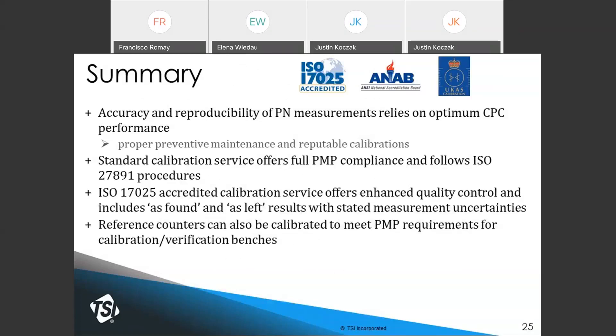In summary, the accuracy and reproducibility of particle number measurement relies on optimum CPC performance. These CPCs need proper preventive maintenance — replacing the internal wick, filters, cleaning nozzles — and then a reputable traceable calibration to a national standard using ISO 27891 procedure, keeping all PMP requirements for CPC calibrations. All TSI calibrations are PMP compliant and follow ISO 27891.